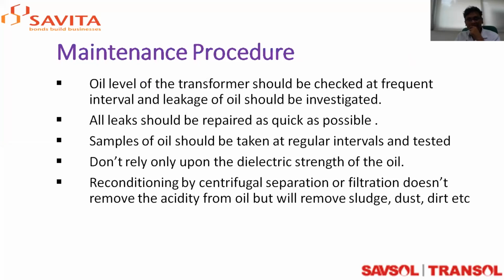The oil level of the transformer should be checked at frequent intervals, and oil leakage should be investigated. In my earlier slide, I mentioned moisture. If leakage is persistent, then air is always leaking from the atmosphere into the transformer, and these leakages will hamper the life of the transformer. So one has to always attend to these leakages, and oil leakage always means loss of oil. Whatever leakage there is, you have to top up the oil, which is again a loss. So everybody has to be vigilant about leakages.